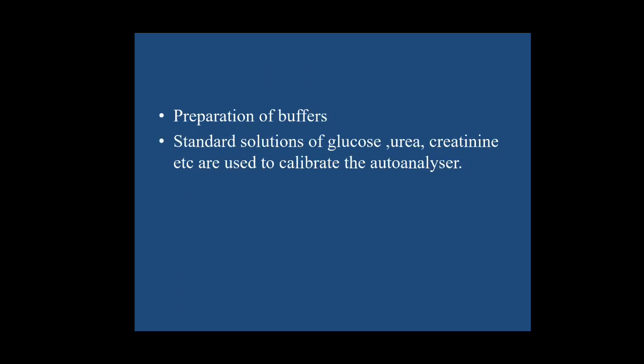And for preparation of buffers also, these buffers mainly in kinetic enzymatic experiments will be used. So there also standard buffers, standard solutions are used. And these standard solutions are also used to calibrate auto analyzers. We do many estimations in the auto analyzer, like glucose, urea, creatinine, and so many tests. If we have to calibrate, we can use the standard solution. The company itself will provide the standard solution or a calibrator solution, so with a known concentration we put it in the analyzer.